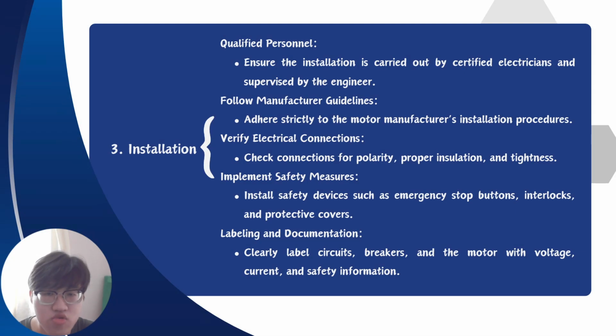Thirdly is go through the installation. Now qualified personnel. It ensures the installation is carried out by certified electricians and supervised by the engineer. Not everybody can install or construct the wiring easily. It needs to be certified and supervised by the certified engineer. Next, follow manufacturer's guidelines. Adhere strictly to the motor manufacturer's installation procedures. Verify electrical connection. The engineer needs to check connection for polarity, proper insulation, and tightness to provide a safe condition.